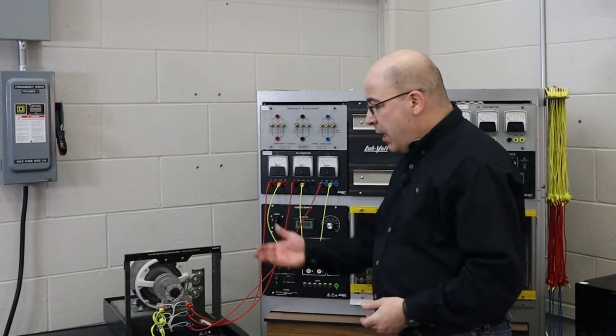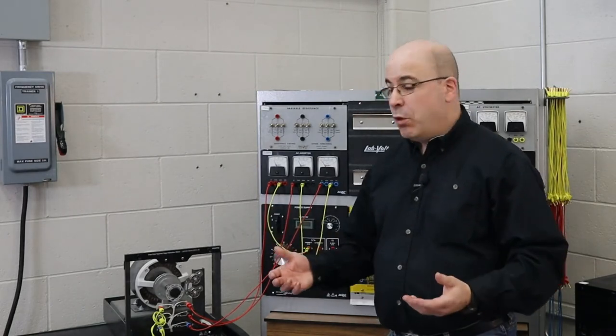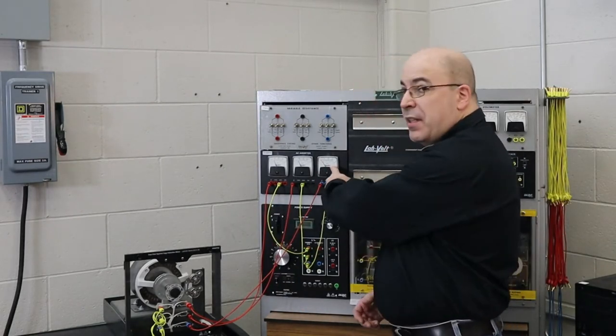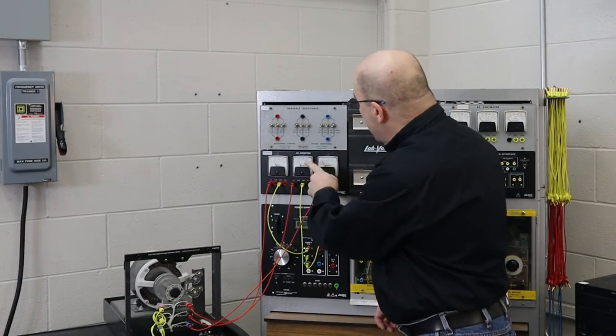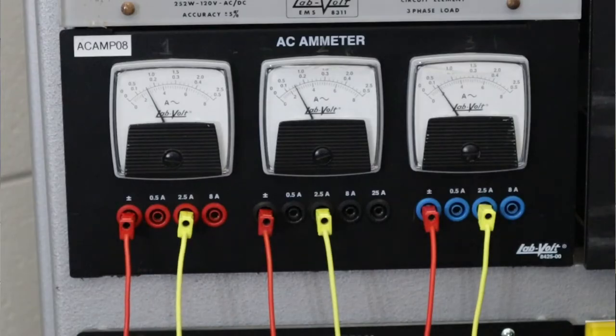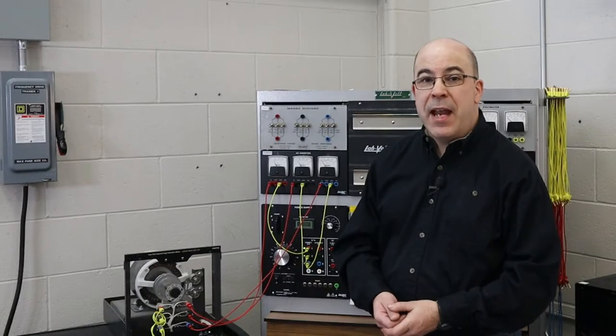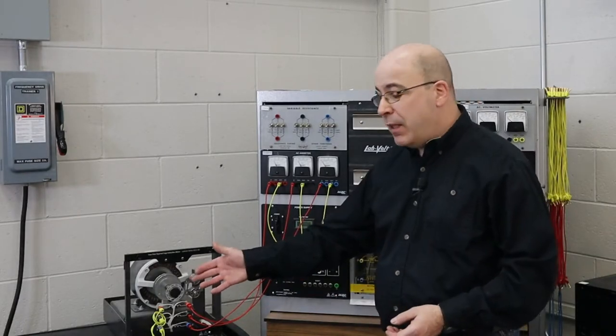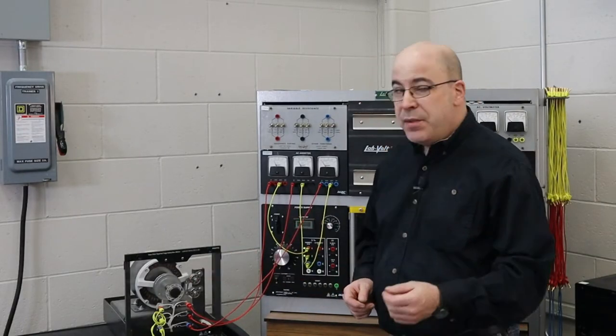Now what we can see is the motor's operating as it normally would be. We saw that there was an inrush of current and it's actually drawing about 0.7 of an amp well within its capabilities. Now here's an interesting thing.